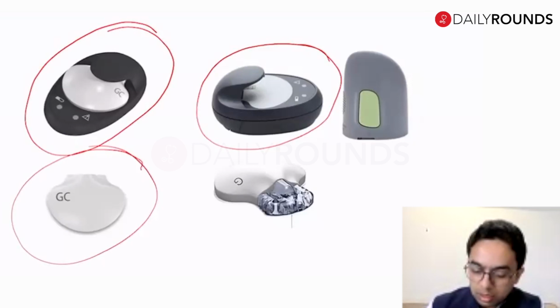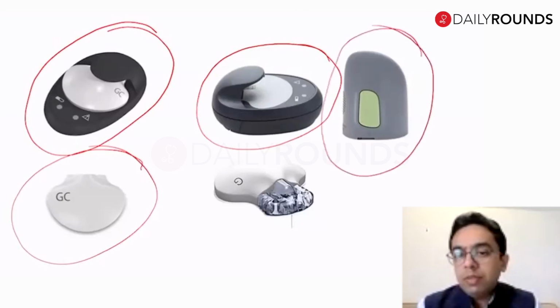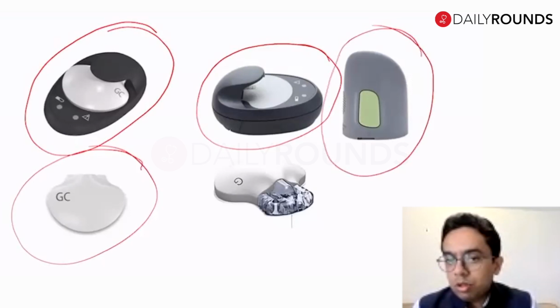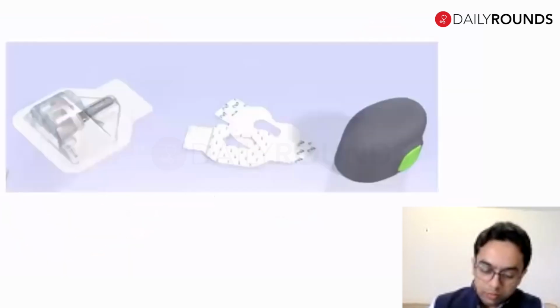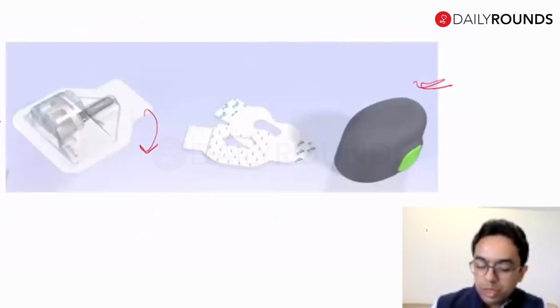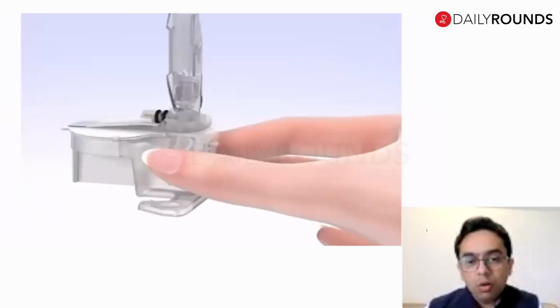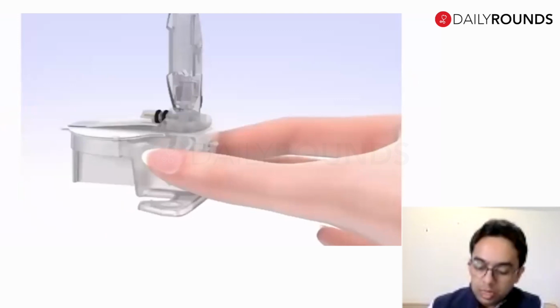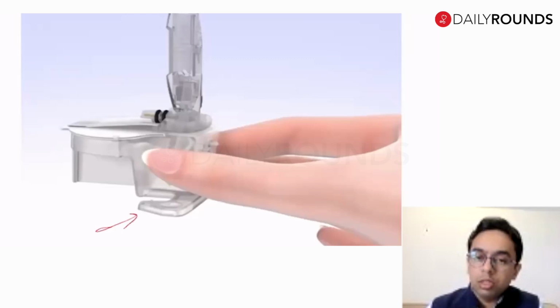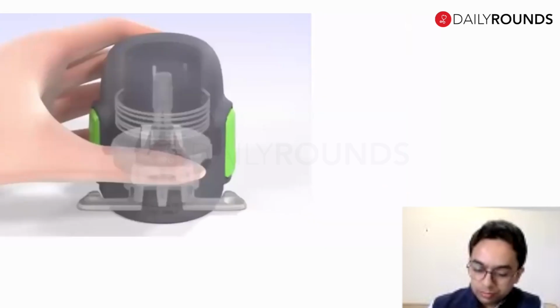And then this is the applicator, like we have there for the Abbott. This is for the Medtronic. So this is how you do it. This is the sensor and this is the applicator. You need to peel off, then you have to place it on the table. And two flanks, you have here, you can see one flank is here, the other on the other side. You have to place your hand and you have to pull it.